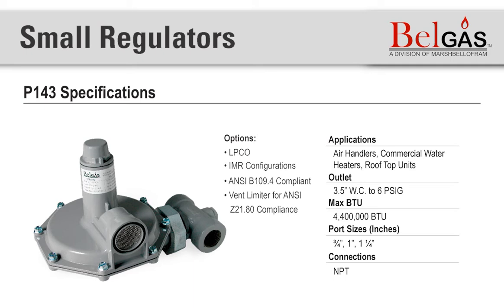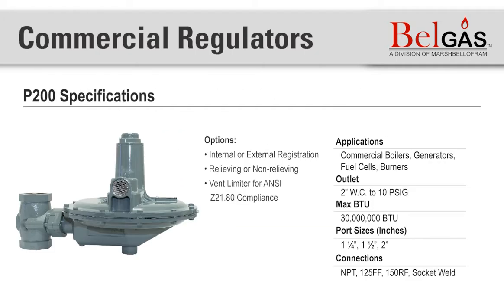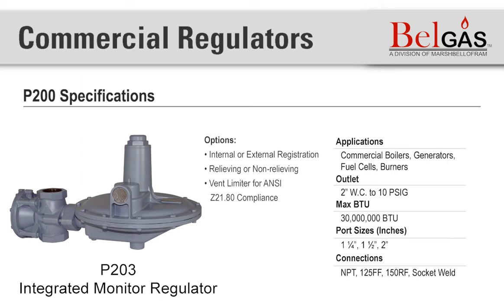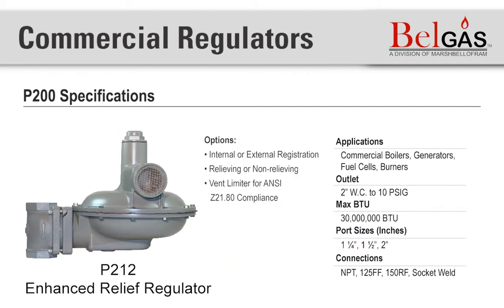Now let's walk through some of the commercial and industrial regulators BelGAS offers, starting with the P200 series. The P200 regulator series is a large diaphragm commercial regulator used for low-pressure delivery. The benefit of the large diaphragm allows consistent pressure through your flow range. The P200 series is also the base for other P200 commercial type regulators, such as the P201, which is non-relieving; the P202, which is relieving; the P203, which is an integrated monitor regulator; the F200, a pilot-operated commercial regulator; and the P212, an enhanced relief regulator with an optimized design to maximize relieving capabilities in an over-pressure situation.